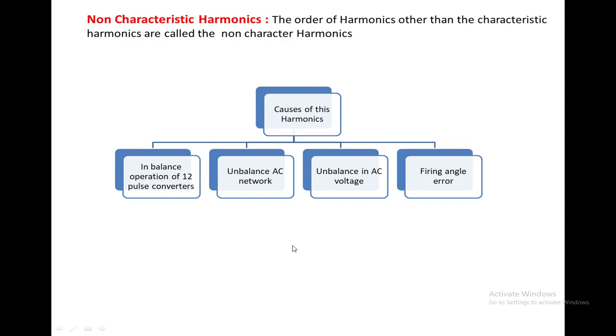The first reason for generating non-characteristic harmonics is the imbalanced operation of a 12-pulse converter. A 12-pulse converter consists of two 6-pulse converters. The imbalanced operation of these two converters generates the non-characteristic harmonics.